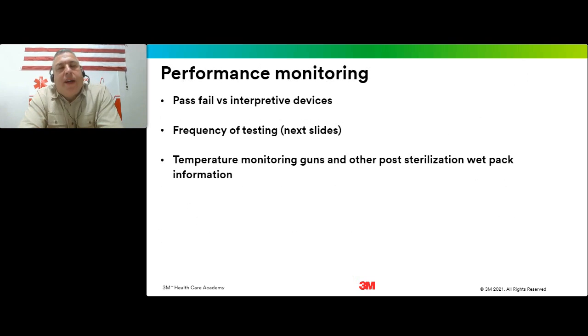Performance monitoring. All right, so there's devices on the market that have pass-fail and then interpretive devices. The pass-fail devices are more or less devices that, let's say it's a white dot, and once it goes into the sterilizer, it turns a black color. That's kind of a pass or fail.